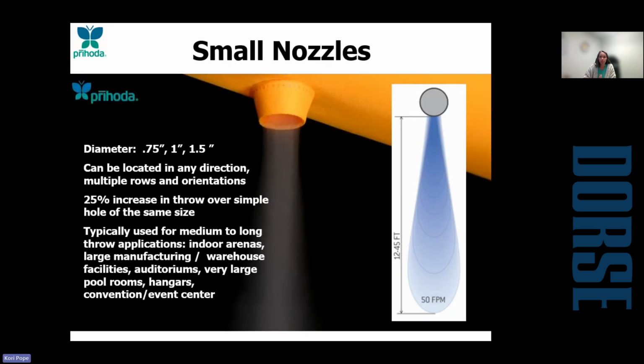We have a few different versions of our nozzles. The first one that I'm going to talk to you guys about is our small nozzles. These are available from 0.75, 1, and 1.5 inches in diameter, and again, can be located at any orientation on the duct with as many or as few rows as we need. These can throw upwards of 45 feet.